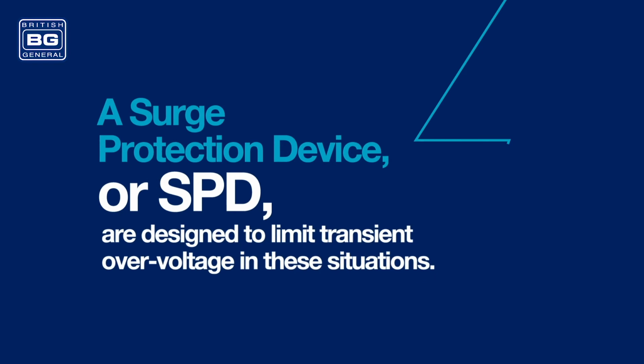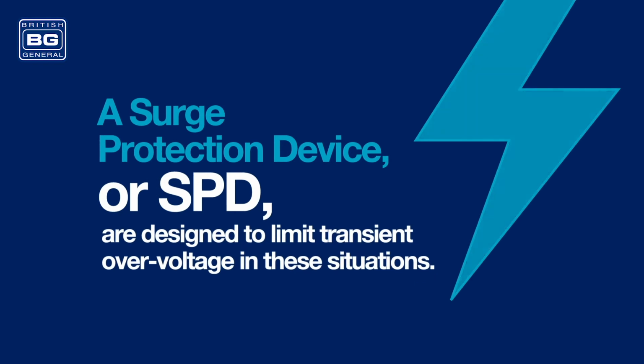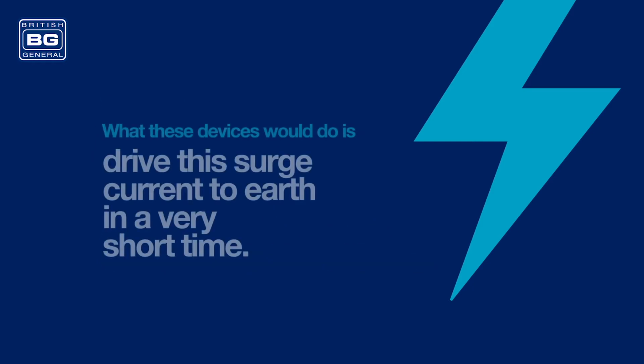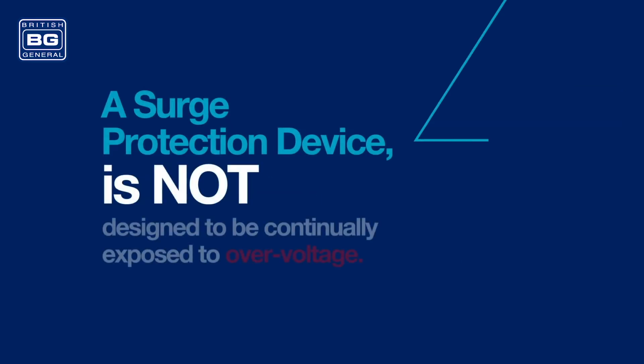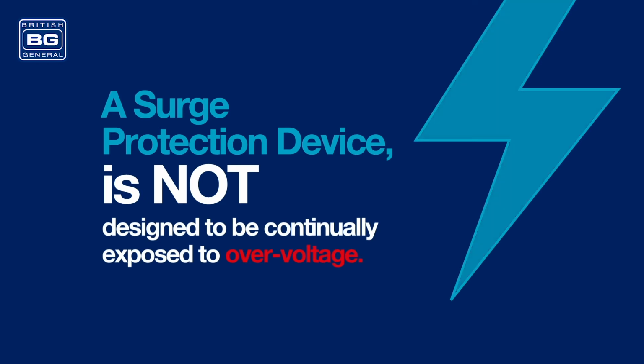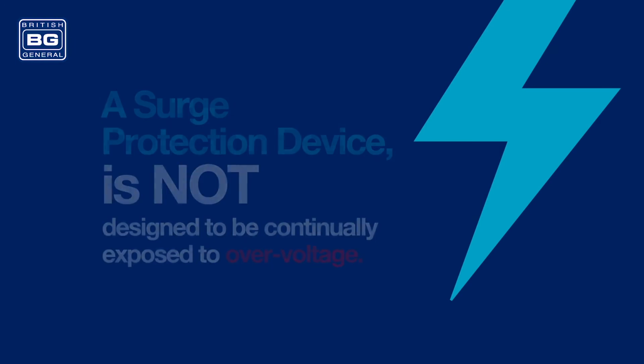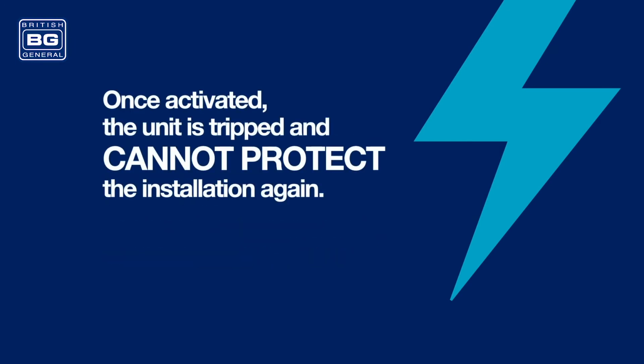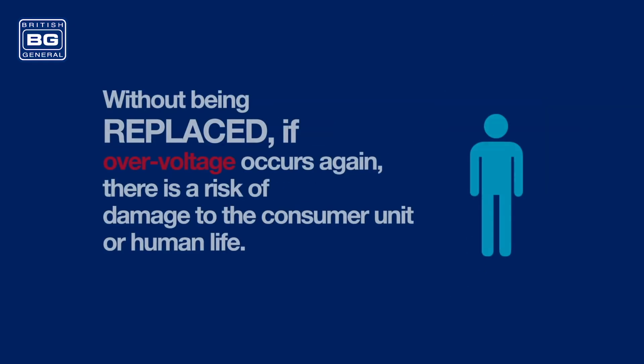A surge protection device, or SPD, is designed to limit transient overvoltage in these situations. What these devices do is drive this surge current to earth in a very short time. That said, a surge protection device is not designed to be continually exposed to permanent overvoltage. Once activated, the unit is tripped and cannot protect the installation again. Without being replaced, if overvoltage occurs again, there is a risk of damage to the consumer unit or human life.